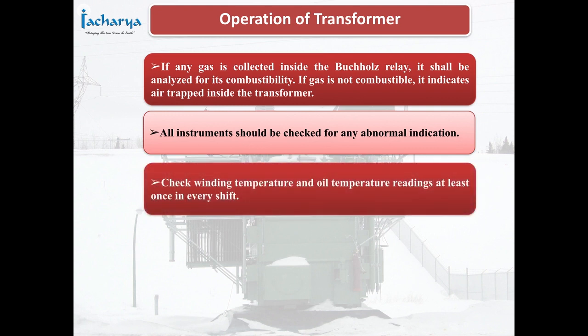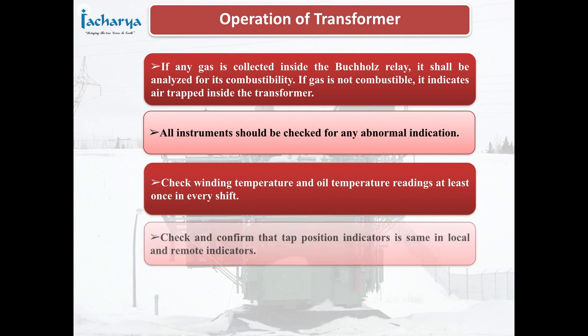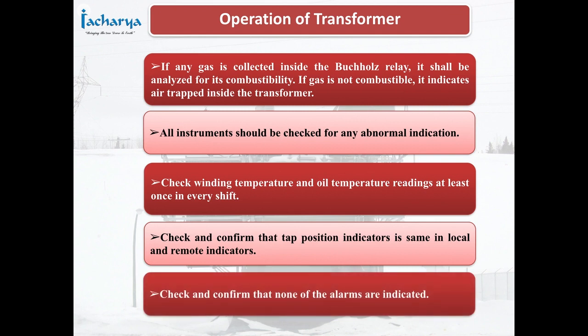Check winding temperature and oil temperature readings at least once in every shift. Check and confirm that tap position indicators is same in local and remote indicators. Check and confirm that none of the alarms are indicated.